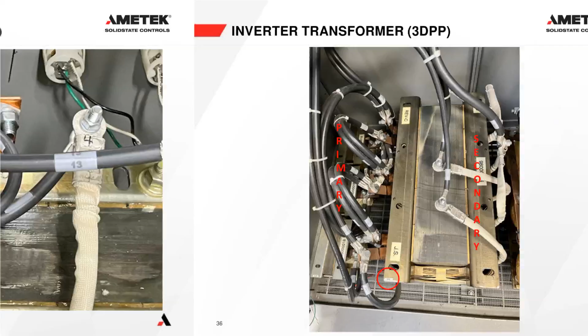For our three-phase system, once again you can see TF2 here, and instead of just having a hot and a neutral, now we have three phases. So our primary is on the left-hand side, basically with 1, 2, 3 tabs there. Then the secondary is basically this terminal here and this terminal here - A phase, B phase, and C phase.